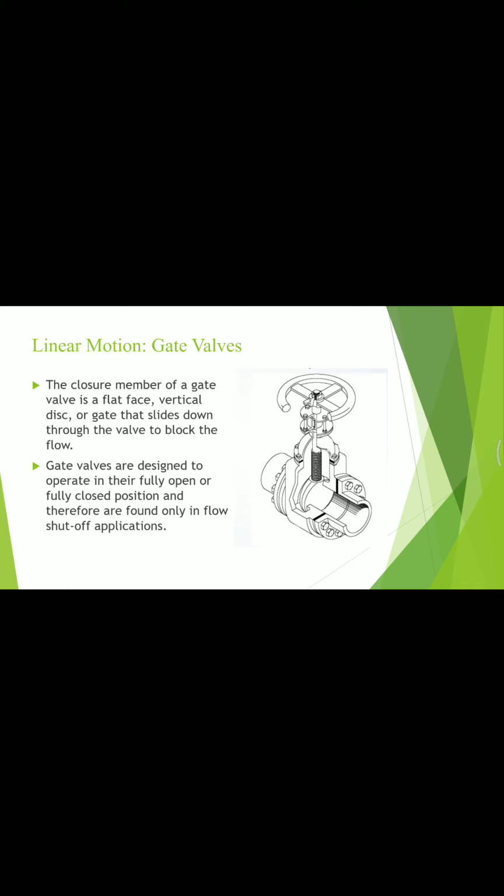Okay, gate valves. The closure member of gate valves is a flat face vertical disc or gate that slides down through the valve to block the flow. Gate valves are designed to operate in their fully open or fully closed position and therefore are found only in flow shutoff application. And we see an example of gate valves.